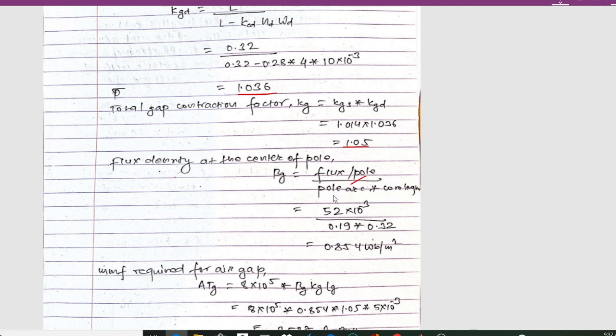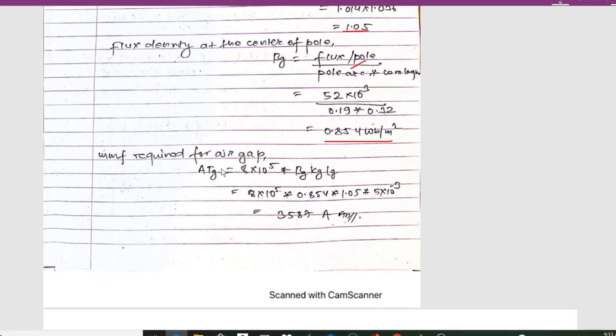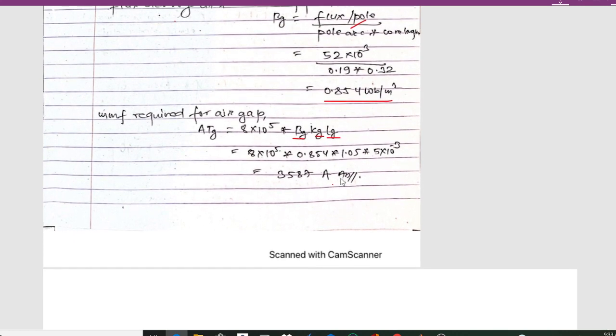Flux per pole is 52 mWb = 52 × 10⁻³ Wb, pole arc = 0.19 m, core length = 0.32 m, giving Bg = 0.85 T. The MMF required for the air gap is ATg = 8 × 10⁵ × Bg × Kc × lg. Substituting all values, the MMF for the air gap = 3587 amperes.